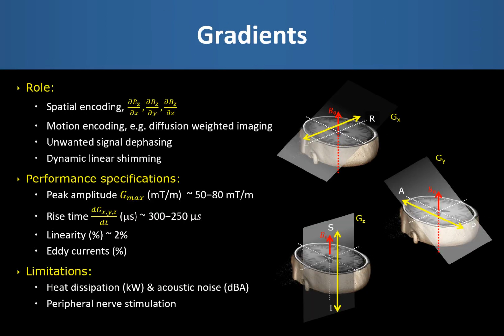The main role of the gradients is spatial encoding. So the gradient fields need to point in the Z direction but spatially vary in X, Y and Z. Gradients can also be used to encode motion, for example in diffusion weighted imaging, and they can also be used to dephase unwanted signals. Gradients can also be used for dynamic shimming to further improve the uniformity of the static magnetic field on a per patient basis.